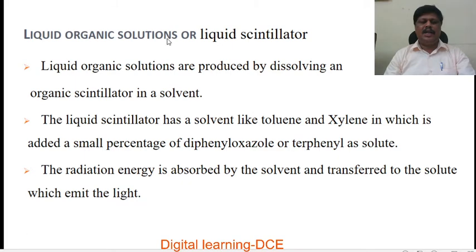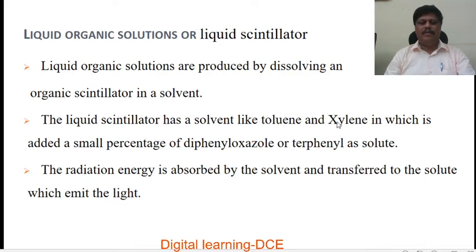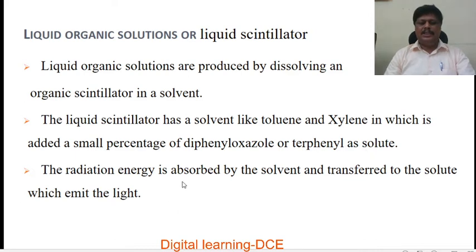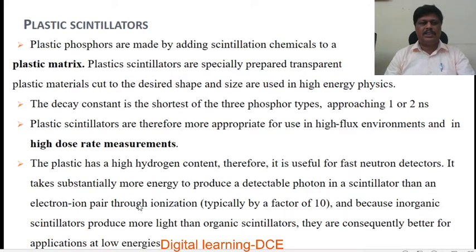Liquid organic solutions, or liquid scintillators, are produced by dissolving an organic scintillator in a solvent. The liquid scintillator has a solvent like toluene or xylene, to which is added a small percentage of diphenyloxazole or terphenyl as a solute. The radiation energy is absorbed by the solvent and transferred to the solute, which emits the light.